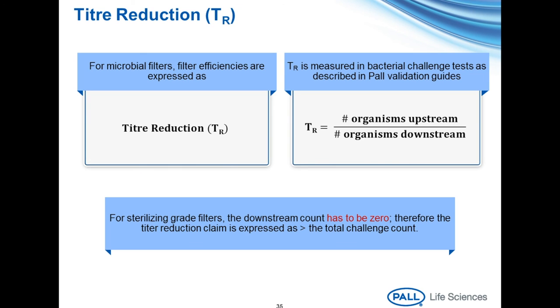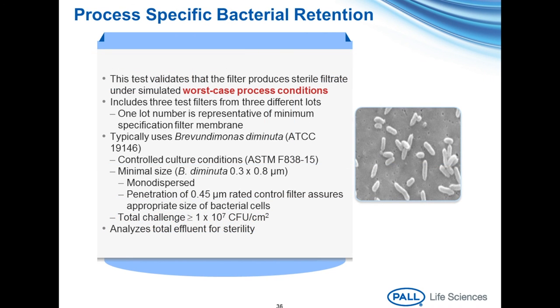Titer reduction can also be expressed as the log reduction value, or LRV. For sterilizing grade filters, the downstream bacterial count must be zero—meaning no bacteria are detected on the analysis filter. In that case, the titer reduction is described as equal to or greater than the total number of influent bacteria.